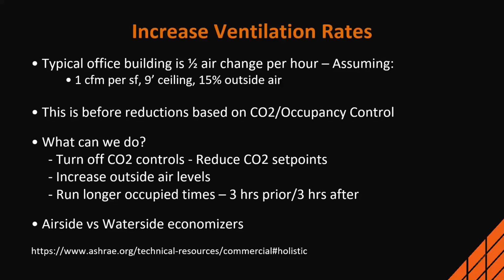The last thing we're going to do is run longer occupied times. And this is where the CDC and ASHRAE differ. The CDC recommends 24/7. ASHRAE recommends 2 hours prior and 2 hours after. Our recommendation is somewhere around 2 or 3 hours prior and after. Being that the virus only lives about 3 hours in the air, after 3 hours you're really not gaining much by ventilating. You've hit the max of what you're going to do. It's either falling out of the air or it's died off in the air.